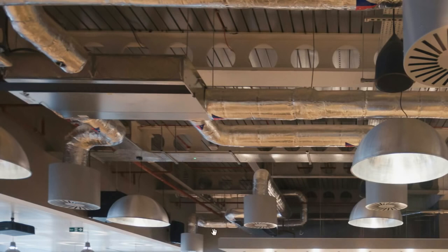If that false ceiling wasn't there, it would look something like this. So we've got a fan coil unit, and we've got the ductwork which is supplying the air. These are also diffusers, they're just slightly different from the square ones we saw just a second ago. So this fan coil unit is sucking up all the air in this space, and it's passing it across here. There's a fan inside, and it's pushing it across a heating and cooling coil, which treats the air to the right temperature that it's set to for this area, and that air is then pushed out through these ductworks to be supplied out through these diffusers where they're required.